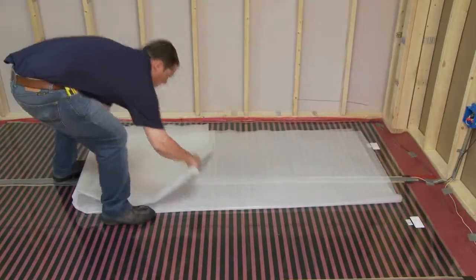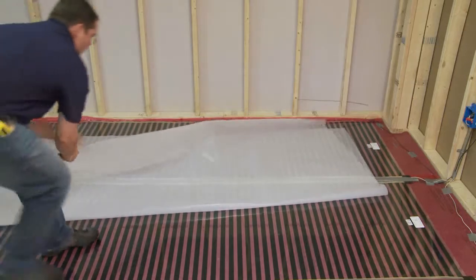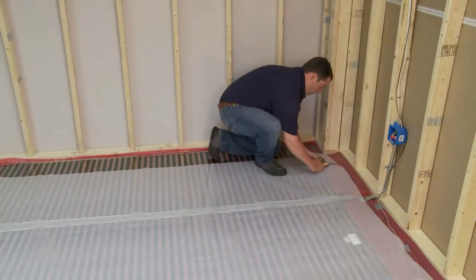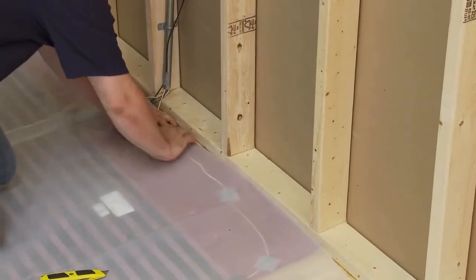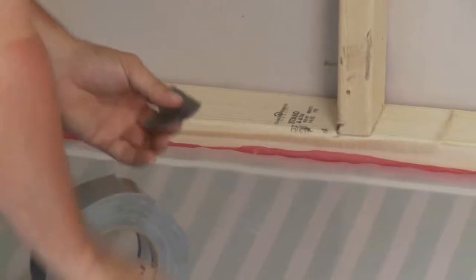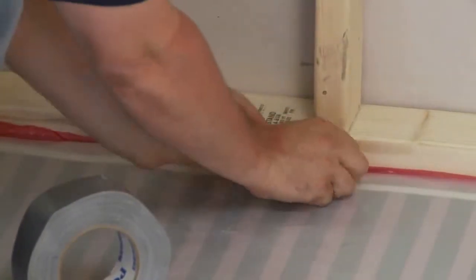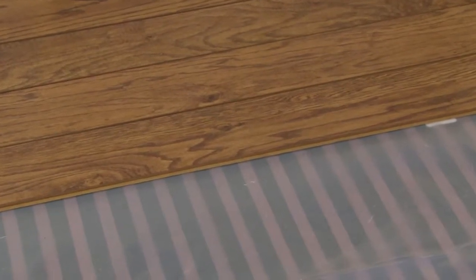To finish the installation, the heating panel must be covered with a polyethylene vapor barrier to provide optimum moisture and additional mechanical and electrical protection. Simply roll out the vapor barrier across the entire floor. Cut to length and overlap adjacent pieces by a minimum of 4 inches. Seal a layer of polyethylene vapor barrier with duct tape over the floor surface, including the heating element and wiring. The installation is now ready to receive the final floor covering. Avoid any unnecessary foot traffic over the area until the final floor covering is laid.